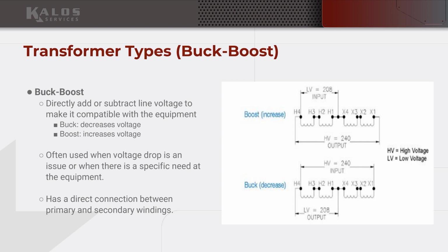And what this allows us to do is take an incoming voltage and either increase or decrease its voltage based on however we're wiring it. In a boost configuration, it looks like this, where line one or your high voltage circuit will come in and land on H4 and between H1 and X4. And then one side of the secondary travels through the winding and also through the induction, increases the voltage on this other outer leg, which then gives you a 208 input and a 240 volt output. Whereas bucking is the same exact transformer. It's just that we move where we terminate the X1 to a different location, and then it in turn bucks the voltage. Okay, that's as much time as I'm going to spend on wiring in this class.